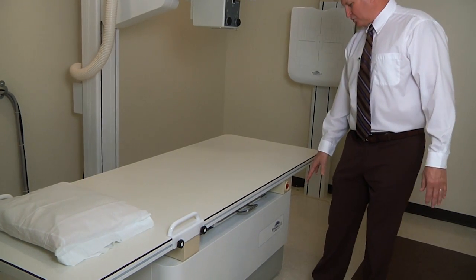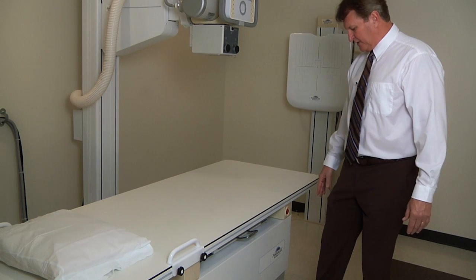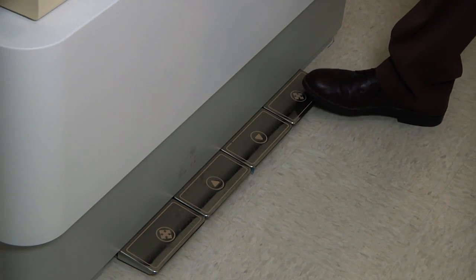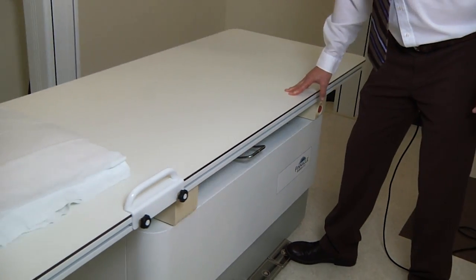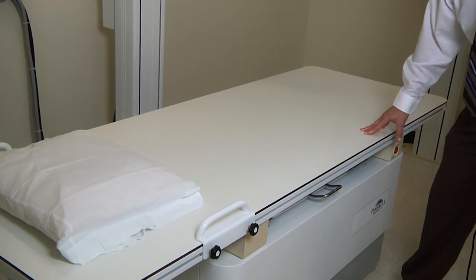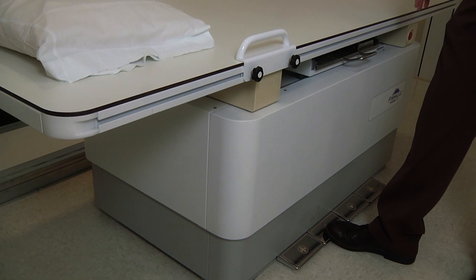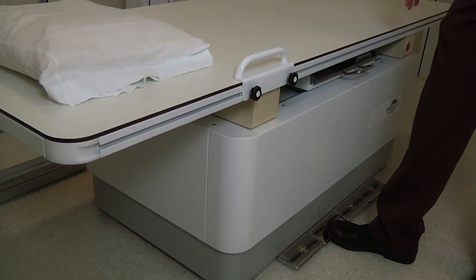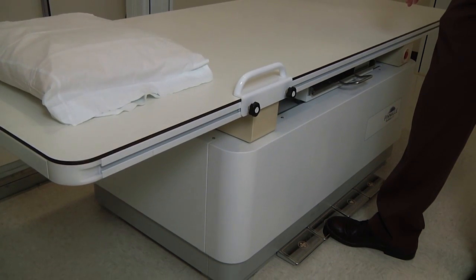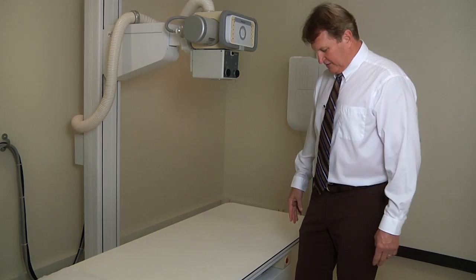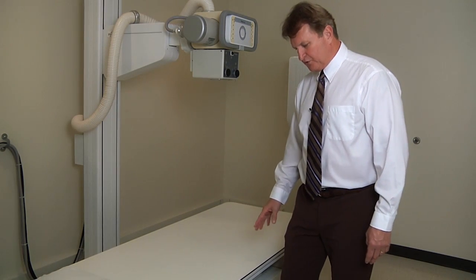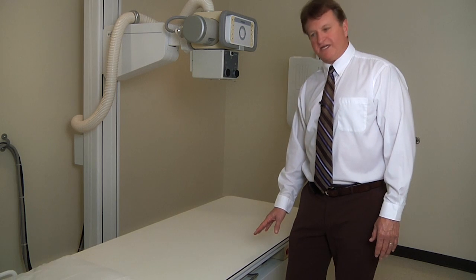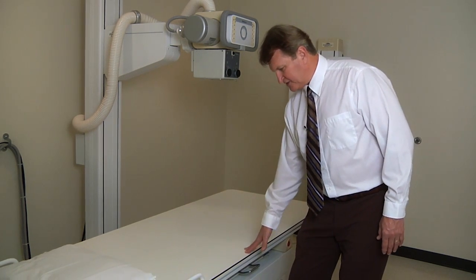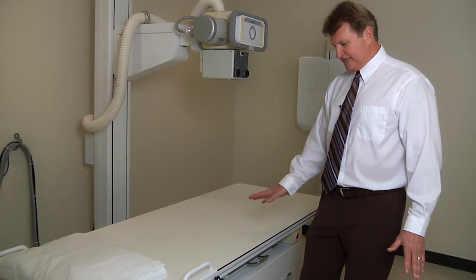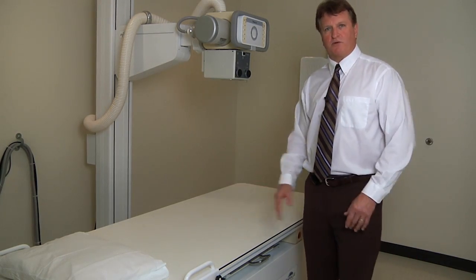The controls for the 4-way float on the elevating table are done with a double tap switch for patient safety. This releases the 4-way float with an audible center. The elevation is controlled with a double tap, and the operation is with a worm gear scissor type operation, which is very quiet and very smooth. There are two operating heights. The first height is for standard operating. It has a second height for stretcher transport.